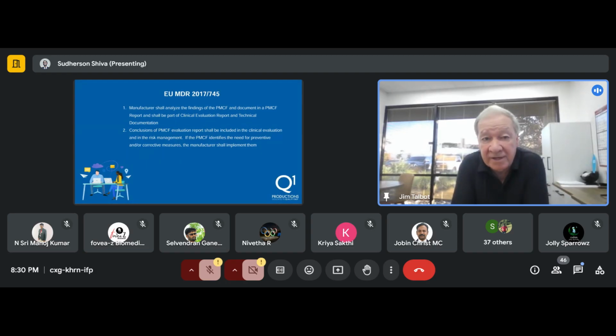And then very important, the conclusions of the PMCF report shall be in the clinical evaluation and also in the risk management. And oftentimes you'll find a need to update your risk management documents or implement corrective actions as a result of a clinical study or gathering clinical data. Discuss that in your PMCF. Next slide.